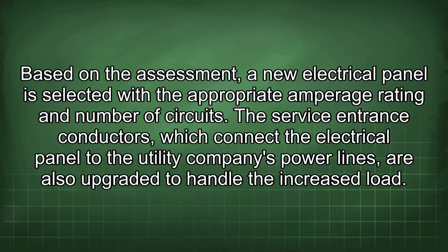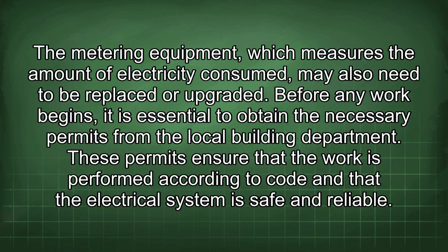Based on the assessment, a new electrical panel is selected with the appropriate amperage rating and number of circuits. The service entrance conductors, which connect the electrical panel to the utility company's power lines, are also upgraded to handle the increased load. The metering equipment, which measures the amount of electricity consumed, may also need to be replaced or upgraded. Before any work begins, it is essential to obtain the necessary permits from the local building department. These permits ensure that the work is performed according to code and that the electrical system is safe and reliable.